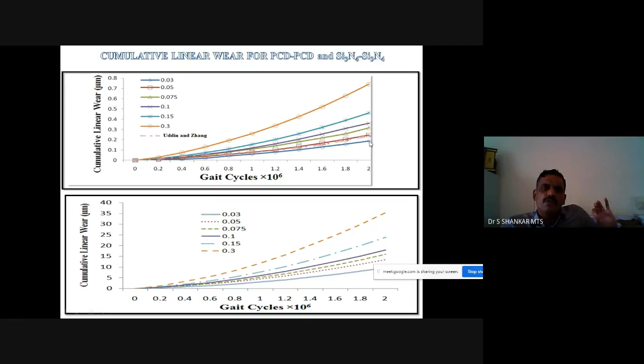So this type of wear will become a guide for surgeons as well as researchers. If you keep on increasing radial clearance, the possibility of wear is around 0.6 microns at the end of 2 million cycles. At the end of 2 years, approximately 0.6 micron wear will happen if there is high radial clearance. If the radial clearance is low, then a minimum amount of wear will happen. So like this, we can try the possible combinations when we compare our results with data.